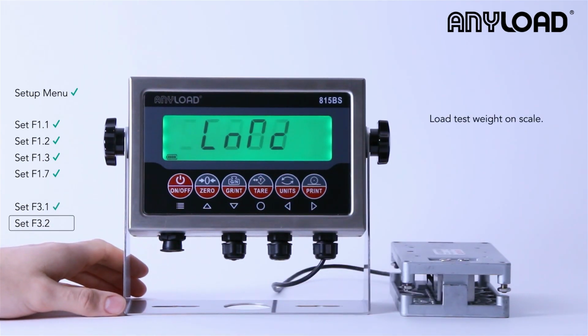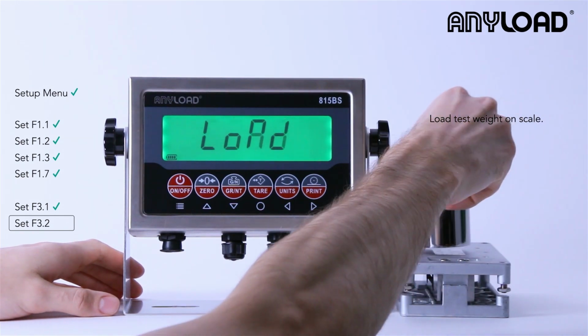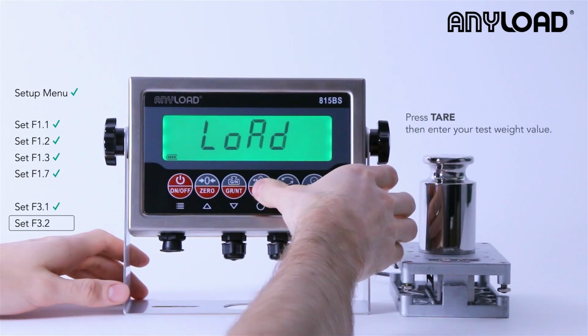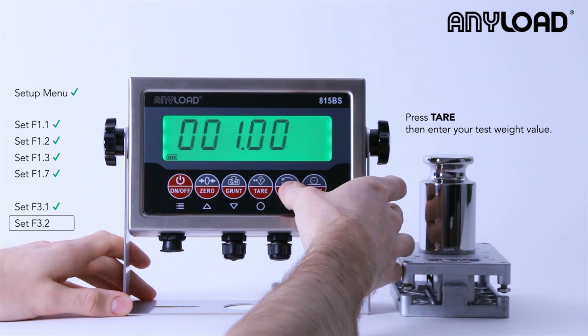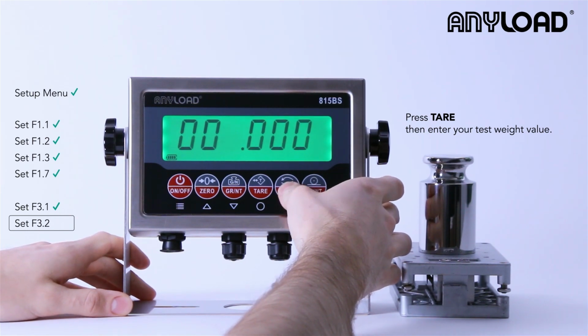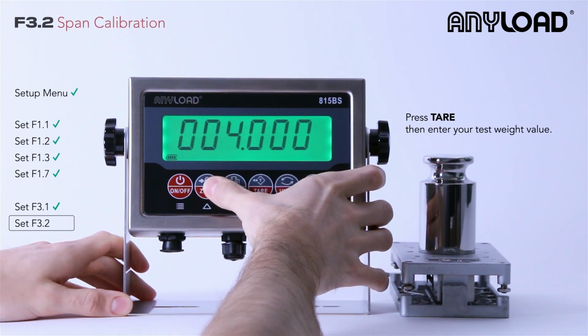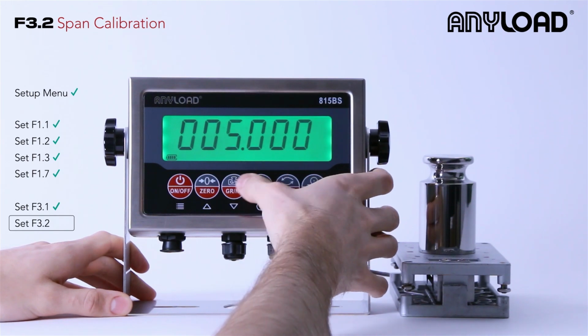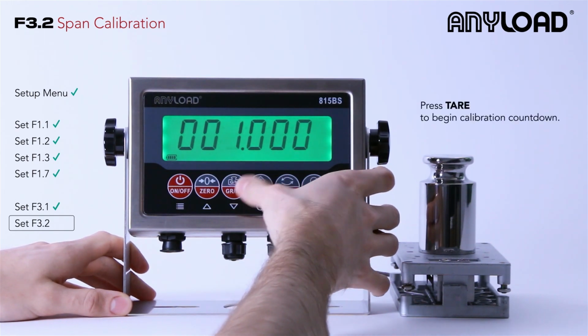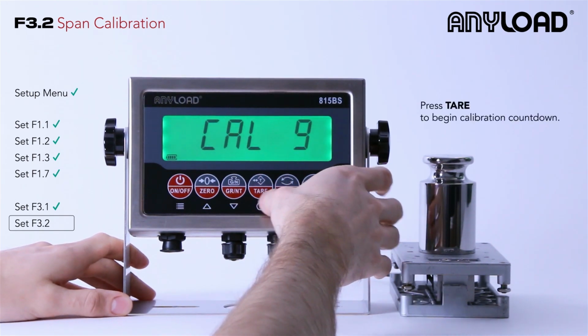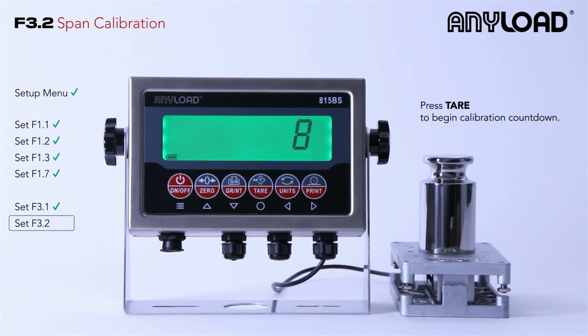You're going to load your test weight on the scale and press tare. And it's going to ask you for the value of that test weight. So in our case, this is just a 1 kg. So we'll navigate back down to 1, press tare to confirm that selection, and it will give us our calibration countdown. Again, don't press anything, don't touch anything while this is happening, let it do its thing.